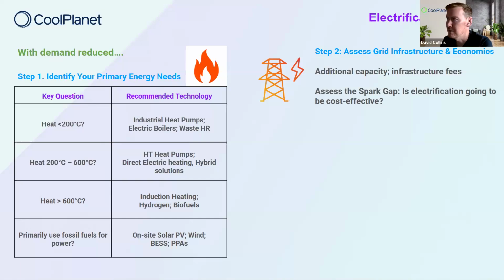But you still need to cater for that additional electricity demand. As part of that, you need to look at the capacity of your site — your maximum demand versus maximum import capacity — and talk to the local network to see, if I'm going to add half a meg or two megawatts of power to my site, will that be catered for? What's the timeline on that?